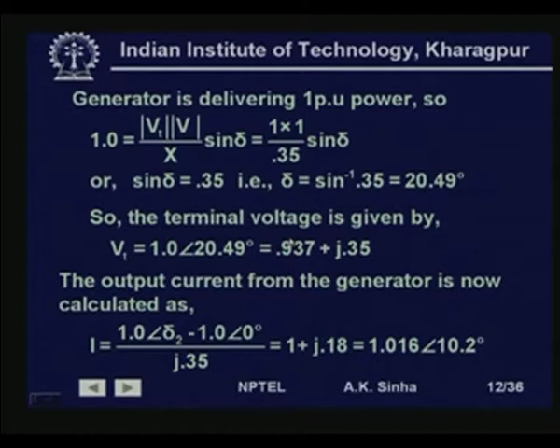The transient internal voltage, that is, the voltage behind the reactance, is equal to the terminal voltage plus the drop in the transient reactance of the machine. The reactance is j 0.15 and the current is 1 plus j 0.18, that is what we had seen here.